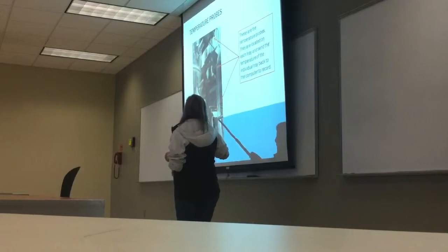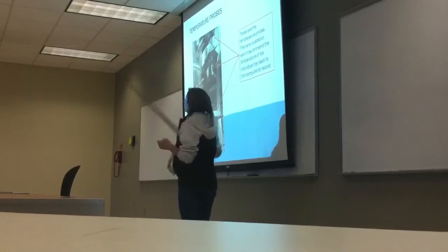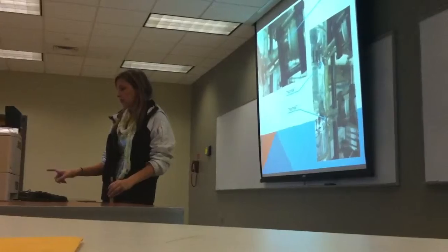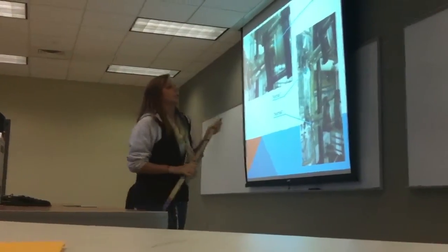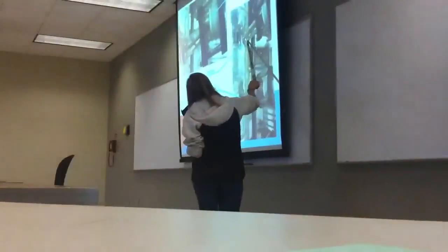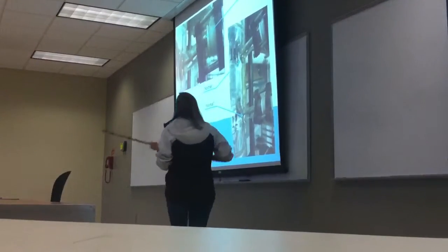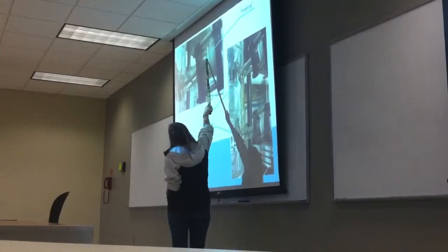Each individual tray has its own temperature probe. And this is just the phenomenon to compare it to two ports that are normal. So this one, there's a little condensate, and then this one, there's just a little liquid level just from where it had bubbled up into it. Whereas this one is completely full.